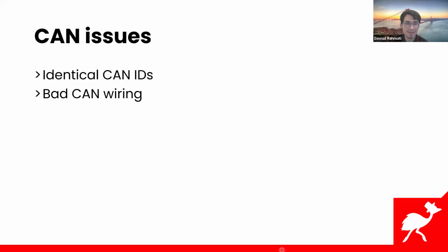Okay. But there's one common thing I'd like to say. Many times I will check connections on the CAN bus, come to find out one connection, the yellow and the green have been reversed, right? Thankfully, it's not like power where you do that and it will fry or something. But if you do that, it will take your CAN bus offline. So this is another very common thing that happens. Somehow someone has connected yellow to green and green to yellow, and it takes your bus offline.